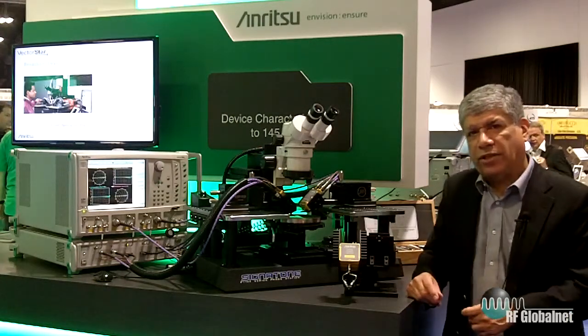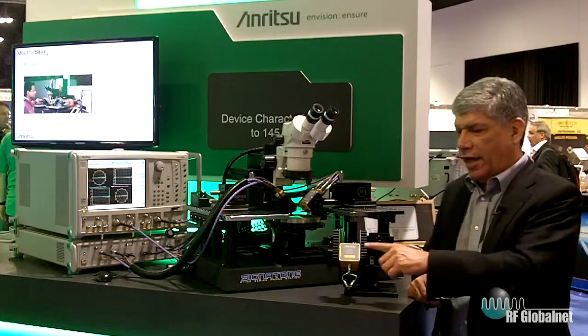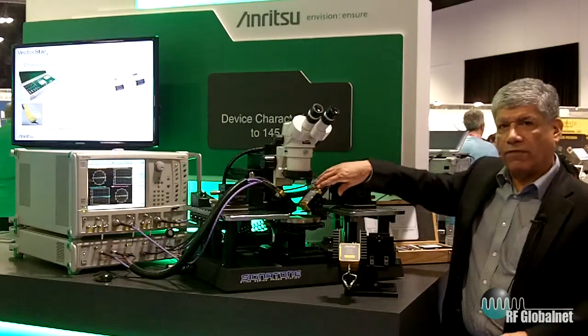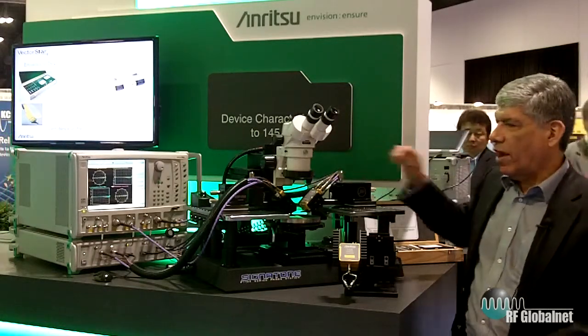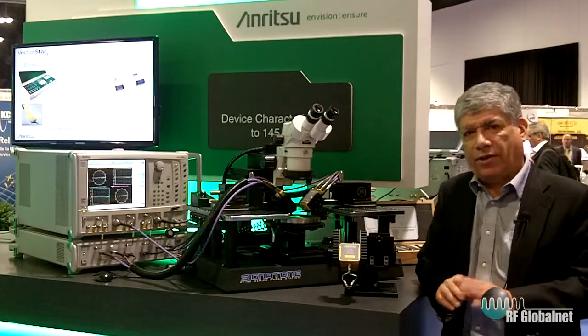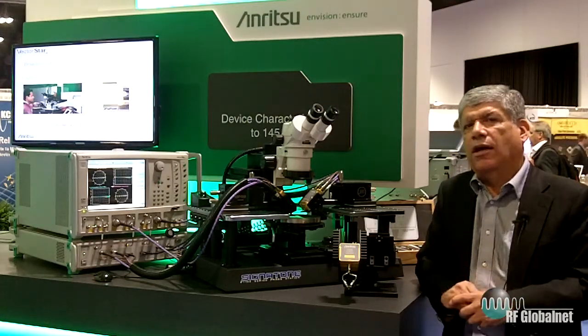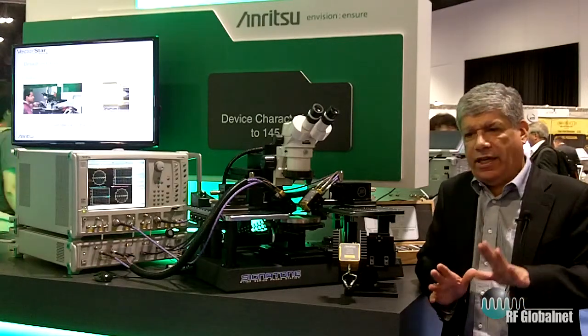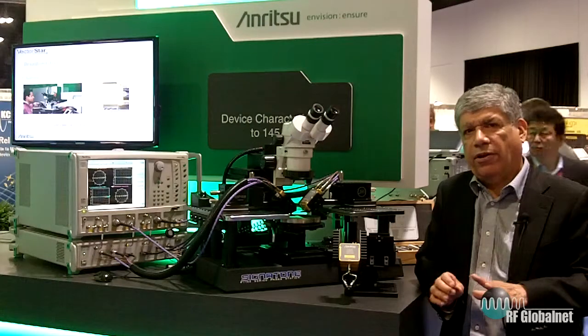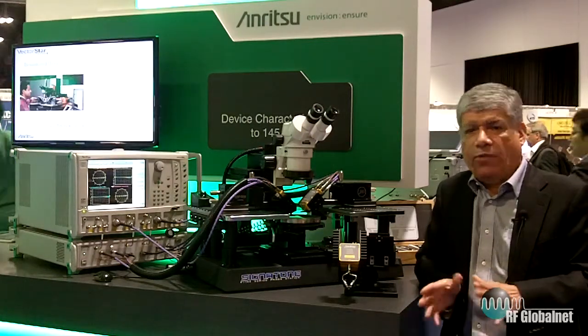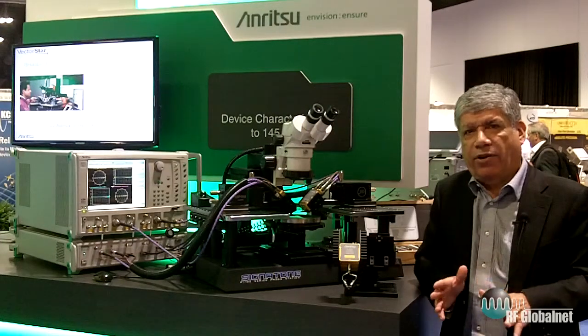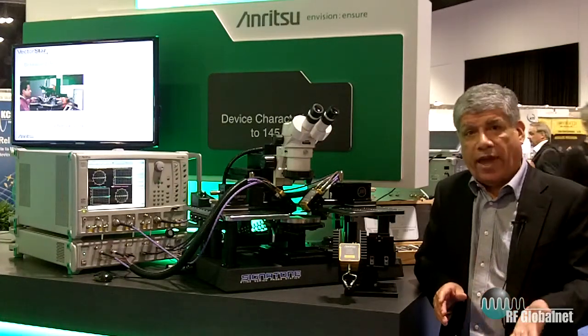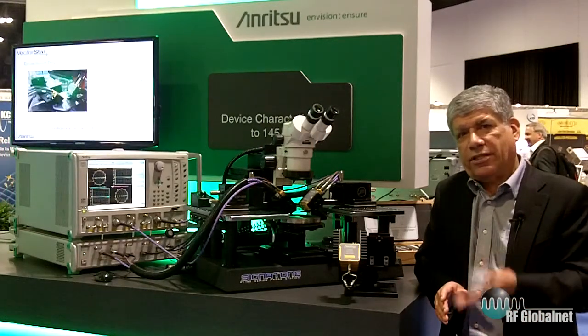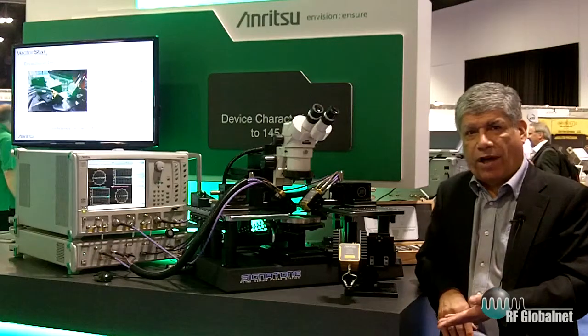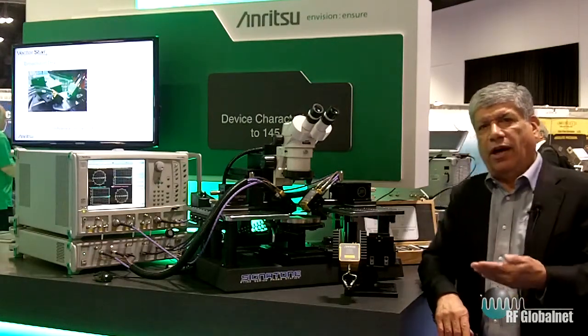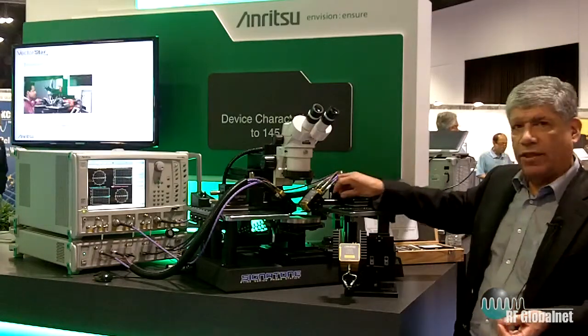And so we've taken that nonlinear transmission line technology, added that next band in, and now have these new modules that go to 145. So with the 145, the issue there is that 1 millimeter connector, which basically can go up to about 110. What we've done is develop and design a new connector, 0.8 millimeter geometry. And Anritsu has always been a pioneer in connector introductions at higher frequencies, starting with the K connector going to 40 gigahertz, the V connector going to 70, and now we have the 0.8 going to 145. So now we have a DC to 145 connector that we can use as our test port in the module.